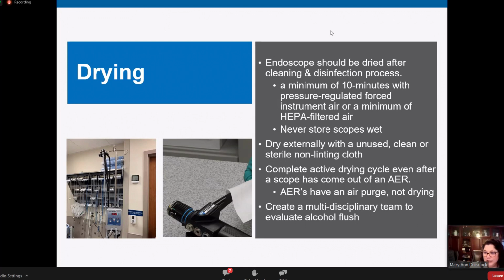It doesn't matter. And I know we'll get probably 10 questions on this. Oh, my scope's going to be used immediately, I'm taking it right back into the next procedure room. Even those have to be completely dried. So think about that time. We already talked about additional time for inspection, additional time for cleaning verification, now additional time for drying every scope. You automatically are going to have lengthier cycles. And I can't tell you exactly how long it's going to be. This step might be 10 minutes, or if you have a drying cabinet, it might be an hour that they have to be in there. You're going to have the additional time for doing your cleaning verification test and waiting the appropriate amount of time to get the result on that. Time to do your inspection. So we need to think about scheduling our procedures appropriately and making sure we have enough inventory of scopes.